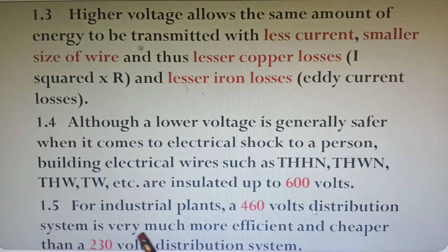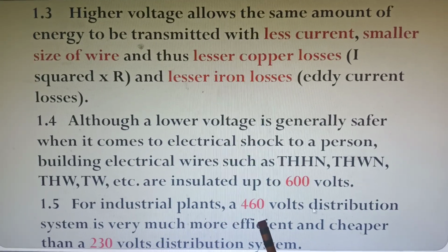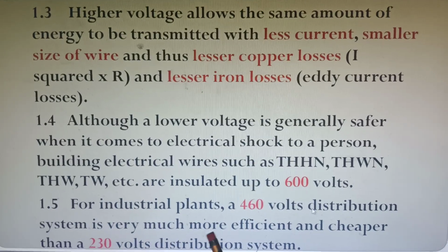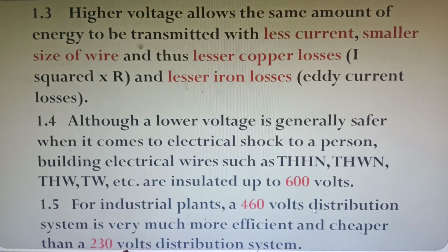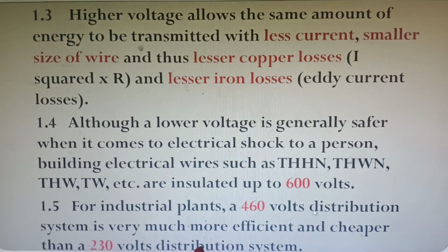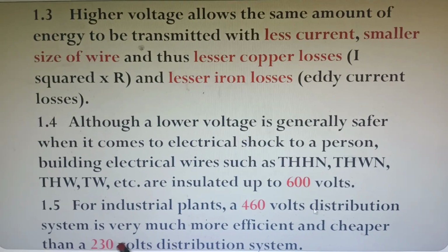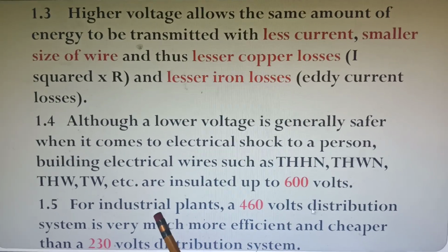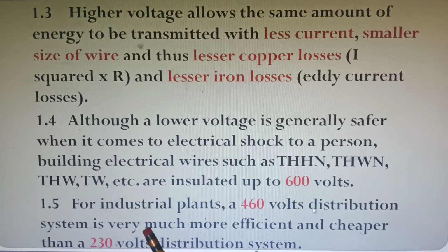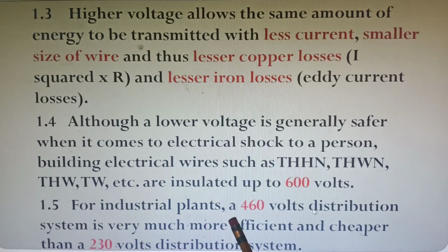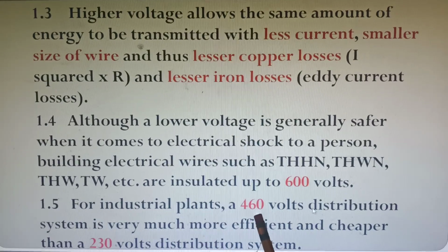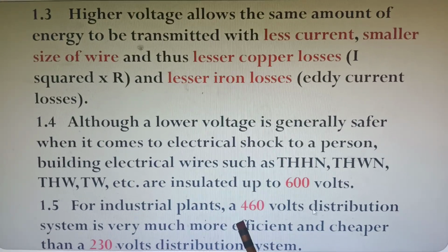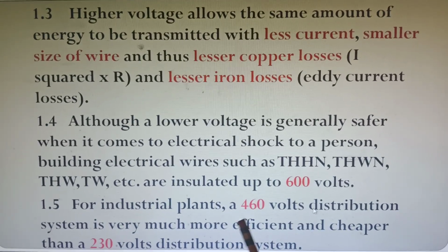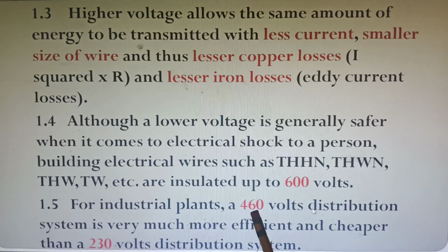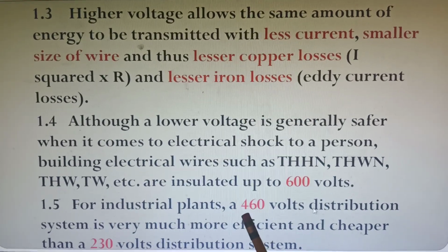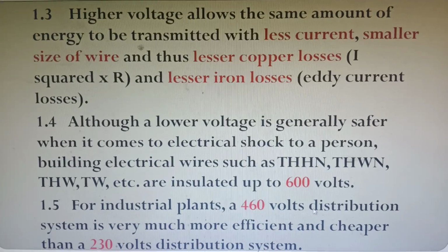Okay, 1.5. In industrial plants, a 460 volt distribution system is very much more efficient and cheaper than 230 volts. Of course, when you're talking of providing lighting loads and small power loads in this kind of plants, there will be a need to provide a step-down transformer from that 460. But usually these transformers are very small, not very big. So there will still be savings in the primary feeders when you use 460 as against 230.